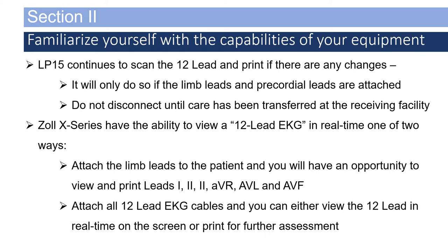The Zoll series has the ability to view a 12-lead EKG in real time one of two ways: either attach the limb leads to view and print leads I, II, III, AVR, AVL, and AVF in 12-lead quality, or attach all 12-lead cables and view the 12-lead in real time on screen or print for further assessment. Either way, if a patient is hooked up to your monitor, do not disconnect until care has been transferred at the receiving facility.